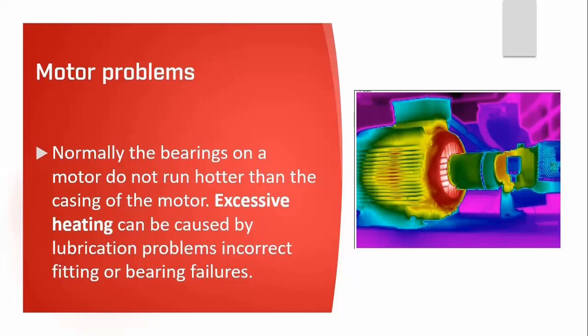For motor problems, lubrication issues include under-lubricated, over-lubricated, contaminated, or incorrect lubricant. Incorrect fitting could be misalignment, imbalance, or structural looseness, and there are many types of bearing failures. While we may detect these problems with thermography, we're unlikely to understand the exact reason for elevated temperature without another form of technology like vibration analysis.